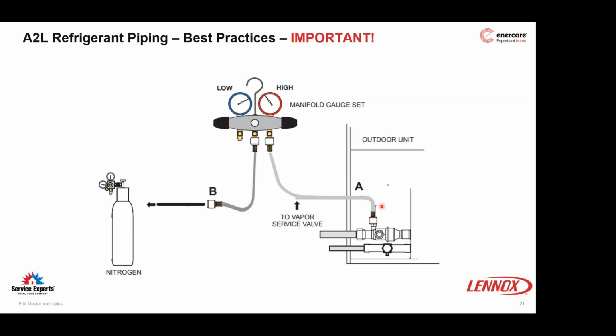So it's not a bad idea. The high side gauge is better equipped for higher pressures. It's a great opportunity to use the right gauge for your testing and minimize the possibility of any sort of damage or a misreading on a low side gauge that isn't maybe as equipped to take on as high pressures.